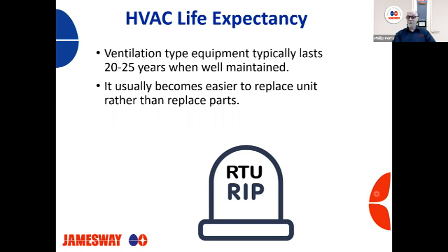I have gone through that to where we exchanged the gas coils, had to call a crane in and replace that exchanger, dismantle the whole unit. Took a couple of days to do. Again, it's the same for the evaporator, condenser coils. They develop leaks. So at that time, it just becomes much easier to replace the unit rather than repair it.